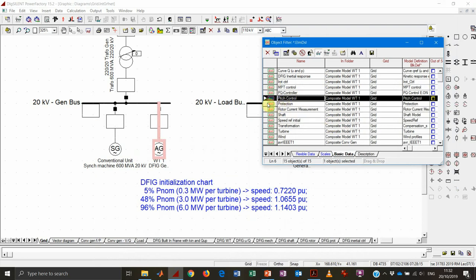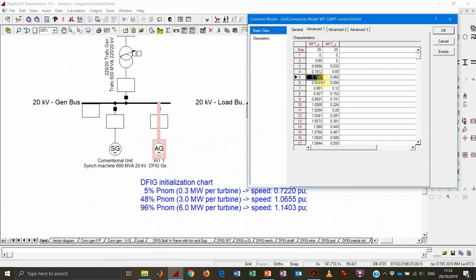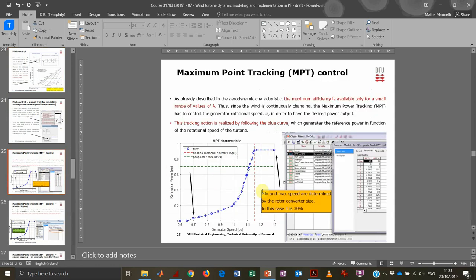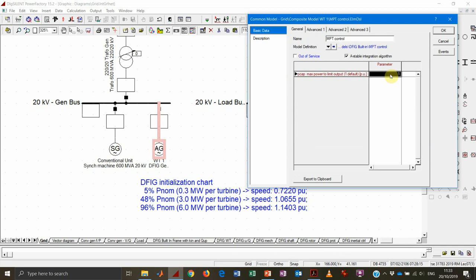The MPT control is the maximum power tracking characteristic — a fairly simple lookup table setting the normalized active power production set point (second column) according to the measured rotational speed. This realizes the MPT curve shown in the slides. There is also a P cap parameter to intentionally limit power production to a lower value than nominal — if kept at one per unit, no capping occurs. This value is normalized according to the complex power of the machine, which is 7 MVA.